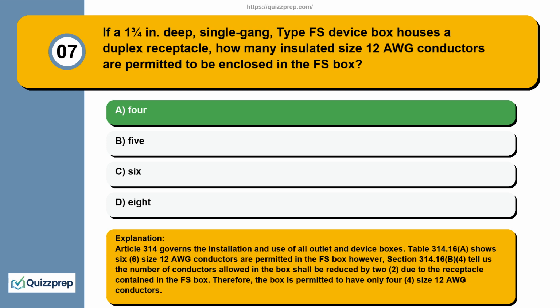Article 314 governs the installation and use of all outlet and device boxes. Table 314.16(A) shows 6 size 12 AWG conductors are permitted in the FS box. However, Section 314.16(B)(4) tells us the number of conductors allowed in the box shall be reduced by 2 due to the receptacle contained in the FS box. Therefore, the box is permitted to have only 4 size 12 AWG conductors.